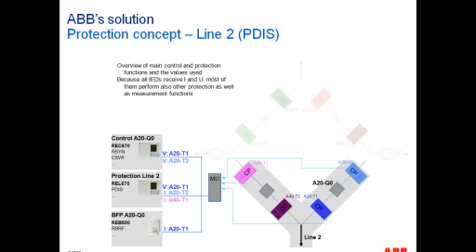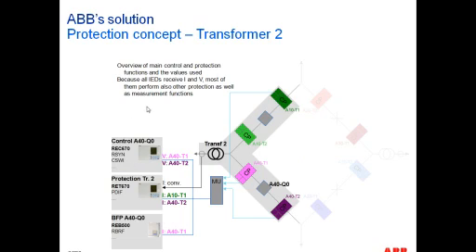Line 2 was essentially a copycat of that particular scheme. And then in the case of the transformer base, what we had was, again, this T1 and T2 sensors going into the merging unit, as well as this A40T1 for the purposes of breaker fail, again. And the merging unit provided the RET670, which is the transformer differential relay, the current samples from the high side of the transformer via sample values, but the low side of the current contributions to complete the transformer differential protection scheme came in the form of conventional instrument transformers onto the relay.